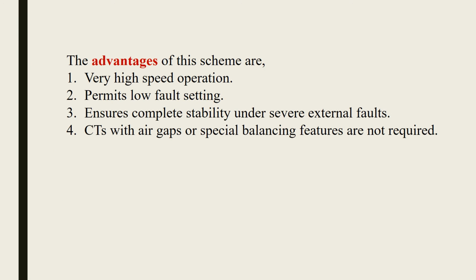Advantages of such a scheme are high speed operation, it permits low fault setting, and it ensures complete stability under severe external faults or through faults. Here we do not require CTs with air gap or any special balancing feature.